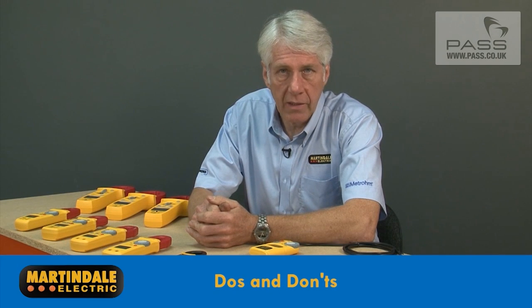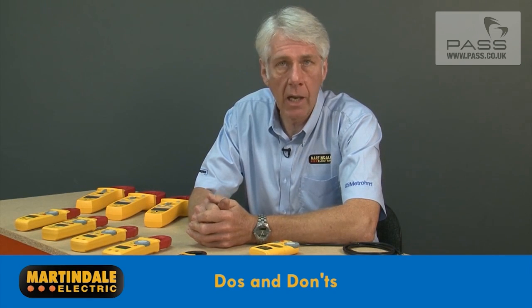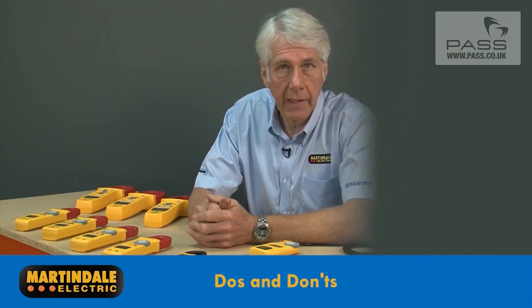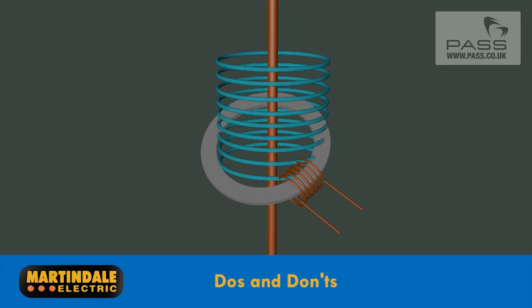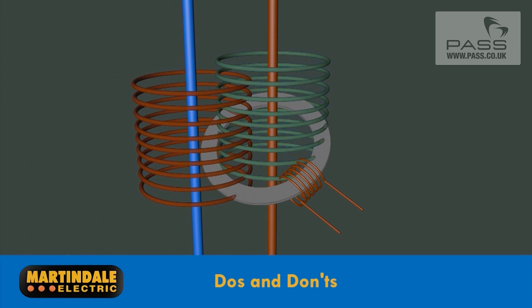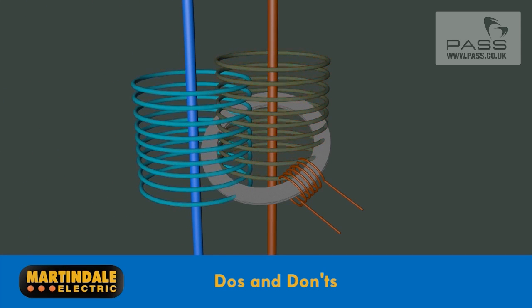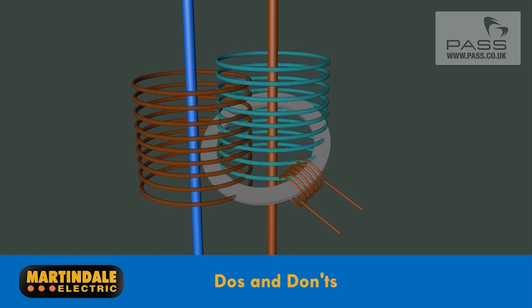With low quality meters, the position of the conductor can cause large errors in readings, and in this case it's always good practice to keep the conductor centrally positioned. Equally, conductors carrying high currents outside the jaw but next to it can cause large errors in readings if the magnetics design and assembly is poor.